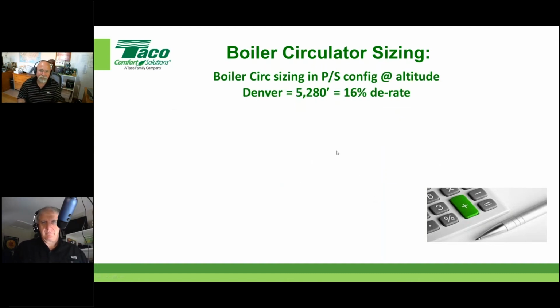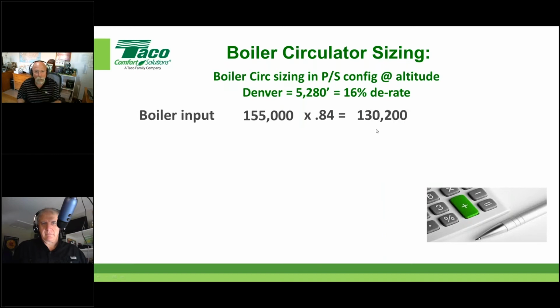If I was at altitude, again, I'm going to go through this pretty quick for the sake of time, I'm running out. You derate for, like, Denver. That altitude there says it's about a 16% derate, so I use 0.84. Now that boiler is no longer a 155, it's a 130,200. Then I also get a kick to the shins for the efficiency. See what I'm doing there?